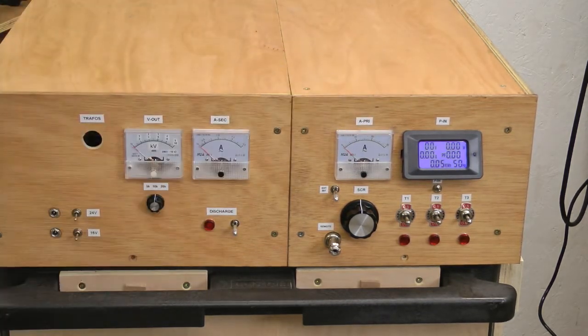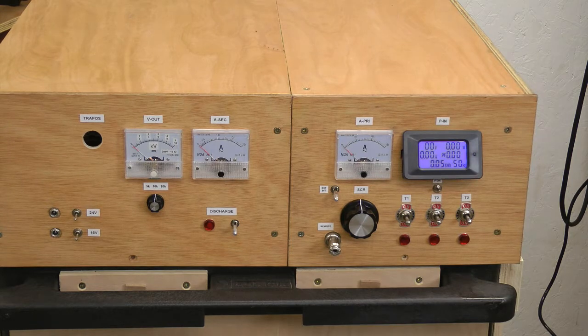I also like to have an analog indication because sometimes when you're working with Tesla coils or with high ambient electric and magnetic fields, this kind of digital equipment doesn't necessarily operate correctly. So I always like to, at the bottom line, have analog instruments as part of the supply, because even if all the power goes, those analog instruments are still going to work, and they're still going to show you what's going on in the supply. For example, particularly on the output, if you've got a large capacitor on there and it's charged up, that's going to show an output, and if suddenly your power goes for whatever reason, the circuit breaker trips or something, that is still going to show you the charge on that capacitor, and that can be considerable.